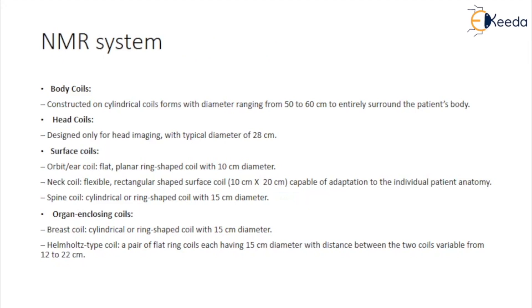Body coils: constructed as cylindrical coil forms with a diameter ranging from 50 to 60 cm to entirely surround the patient body. Head coils: designed only for head imaging with a typical diameter of 28 cm. Surface coil — orbit or ear coil: flat, planar, ring-shaped coil with a 10 cm diameter.